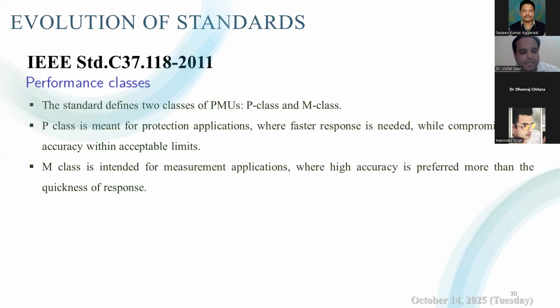This particular standard also specifies two performance classes of PMU, P class and M class. In the P class, P stands for protection. These PMUs are meant for protection and control applications. They are designed to give a very fast response, which is crucial for system protection and fault detection. So mainly this type of PMU, the P class PMU, we utilize for protection and control applications. Obviously, for achieving the fast response, they are allowed to compromise on accuracy up to a certain extent only.